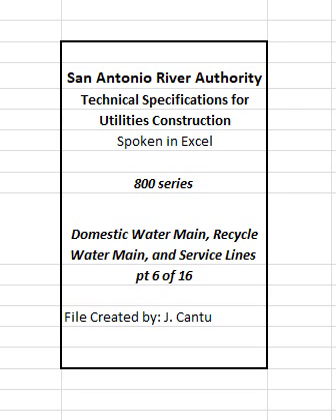2. Width of trench. Trenches shall be of sufficient width to provide ample working space for men engaged in handling pipe and making joints. In no case shall the width of the trench inside sheeting and bracing lines be less than 16 inches greater than the pipe diameter, or as shown in Table 2, trench width.